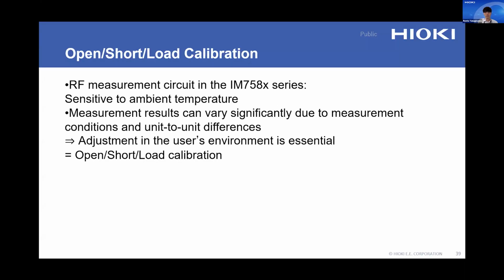So next I will explain the calibration specific to the RF-IV method. In the IM758x series, which supports high frequency measurement, the RF measurement circuit is sensitive to ambient temperature. As a result, the measurement result can vary significantly depending on the measurement conditions and unit-to-unit difference. Therefore, the adjustment in the user's environment is essential. This is performed using open, short, and load calibration.